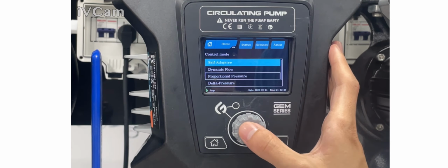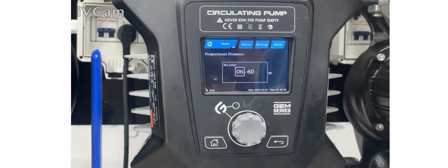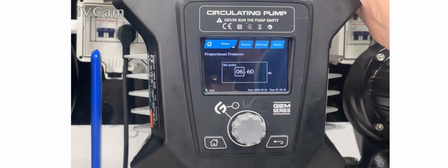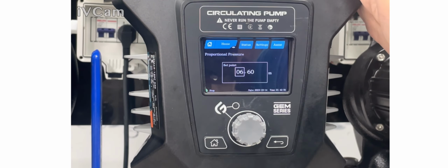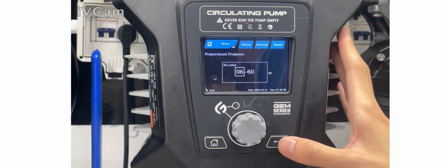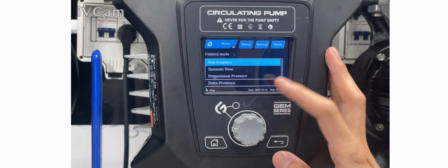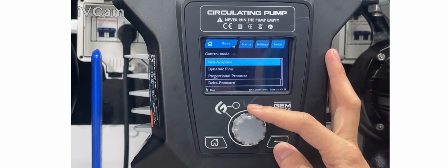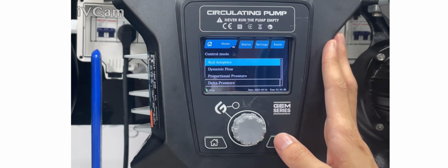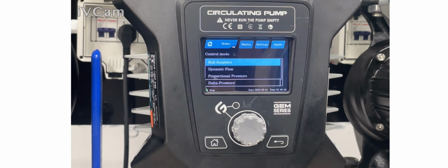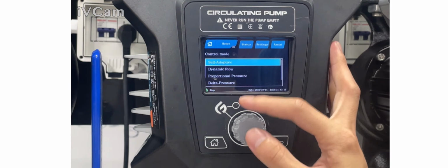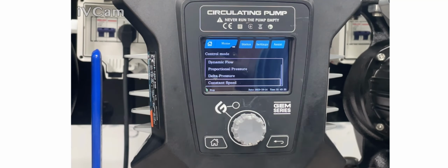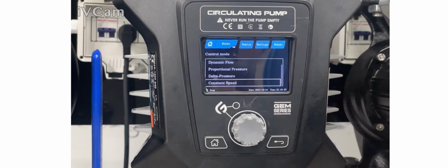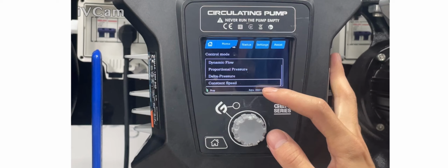Okay, so next is proportional pressure. The system pressure increases as the flow rate increases until it reaches the max power. This applies to systems with relatively large pressure losses in the pipework. So the next is delta pressure. This control mode is recommended for systems with relatively low pressure losses. The pump head is constant and is not affected by the system flow. And the next is the constant speed. The pump operates at a predetermined constant speed curve.